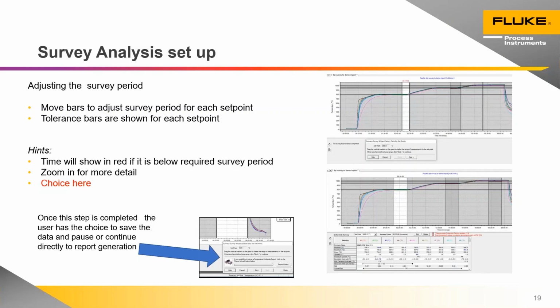And now we get to the bit where there's a bit more human intervention. We set up the stabilization criteria. The software will be looking for these stable periods of readings at each of the set points that are the survey results, if you like. And the graph here shows that you actually have the ability to drag the survey period around, so you can put it into the best position to show the furnace in the best light. The software will automatically warn you if you drag the bars too close together, trying to get a good set of readings. The top graph there shows the time above the little white box is red, showing you that it hasn't met your stabilization criteria for a long enough time.